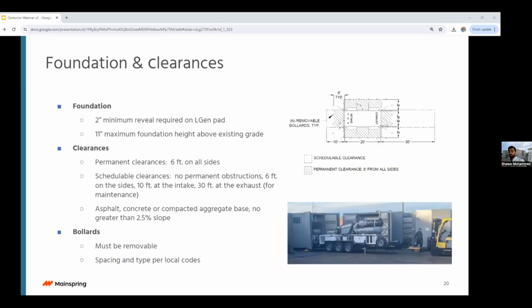From a foundation and clearances point of view, the package is a standard ISO container. So we're looking at 20 feet by 8.5 feet with 9.5 feet height. We require 6 feet permanent clearances around the LGen, and those need to be marked off with bollards. But the bollards need to be removable. And the 6 feet is simply to make sure we have enough clearance for the door.